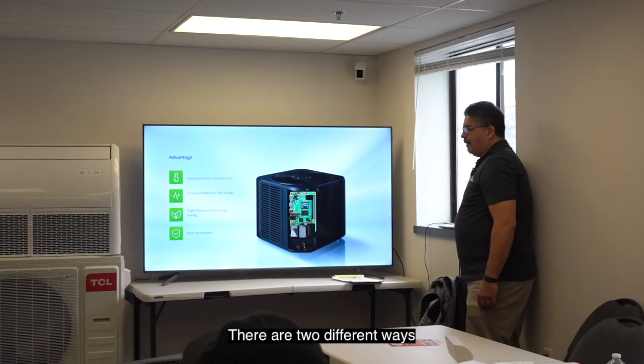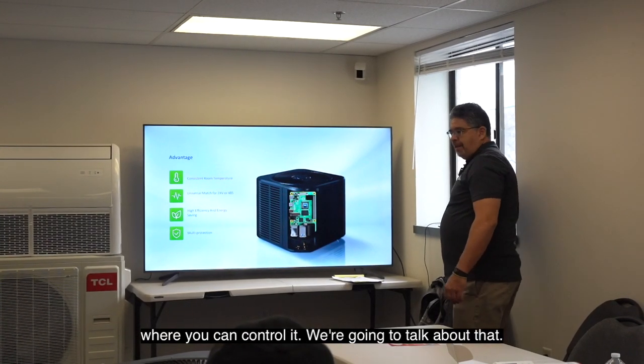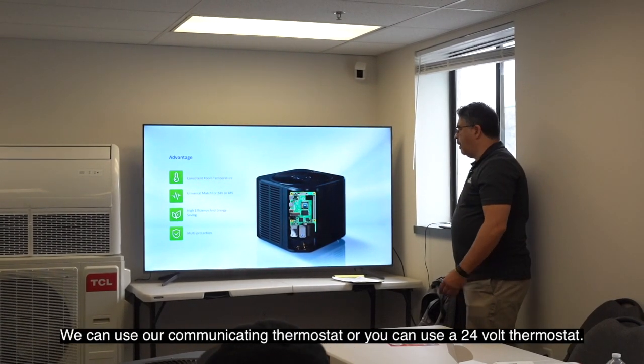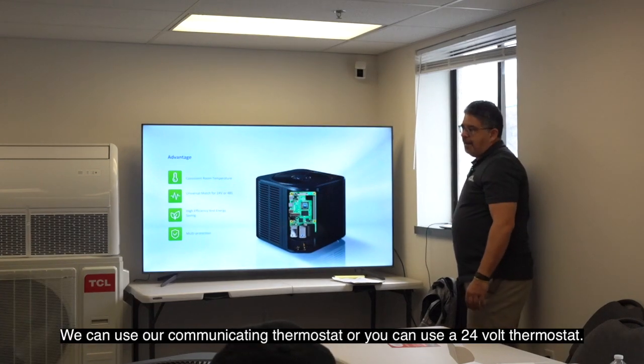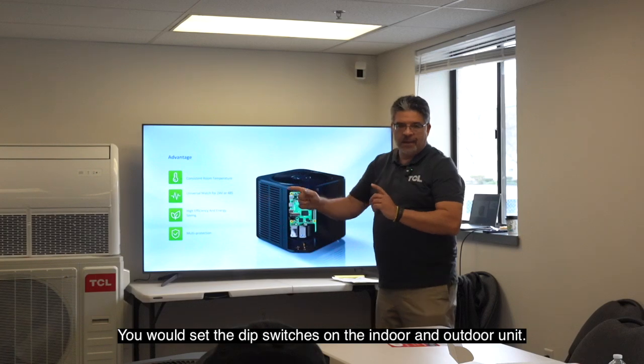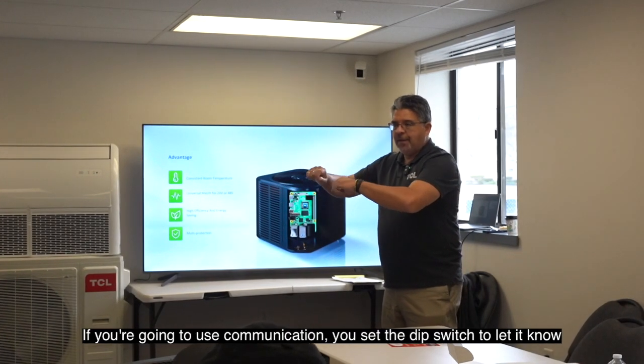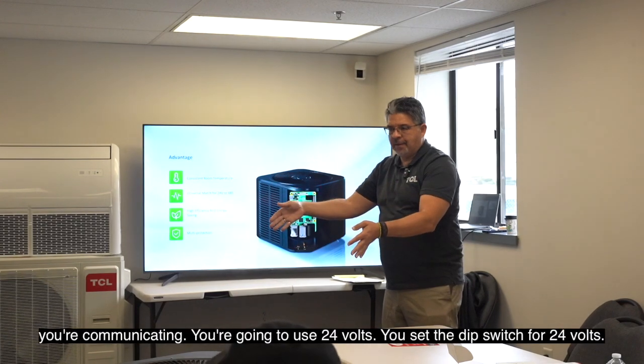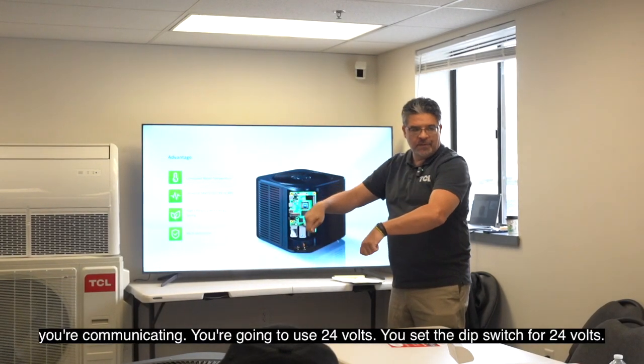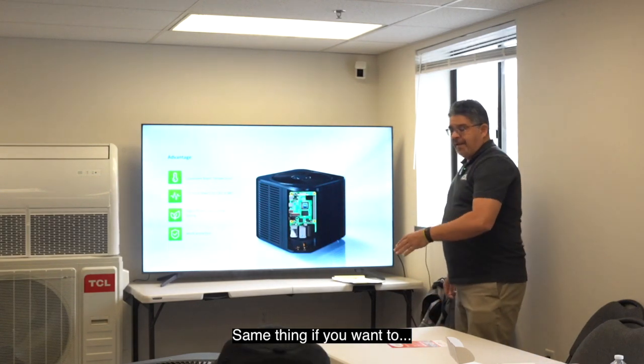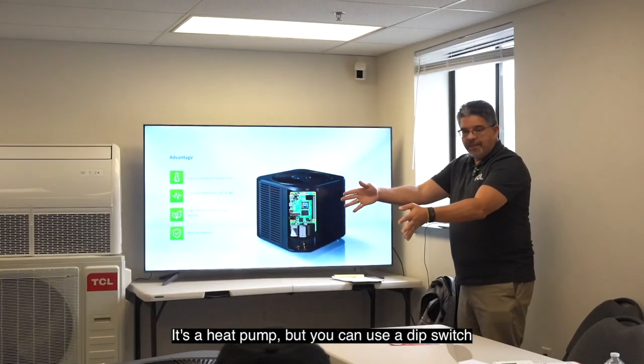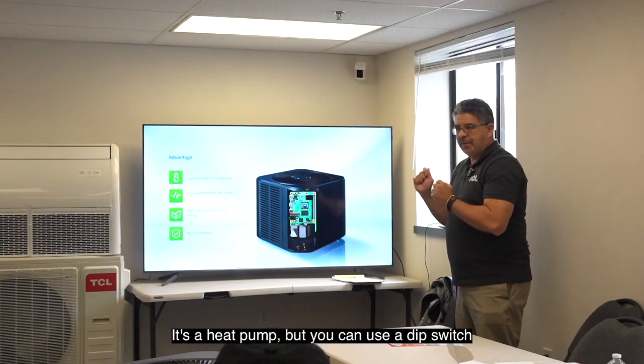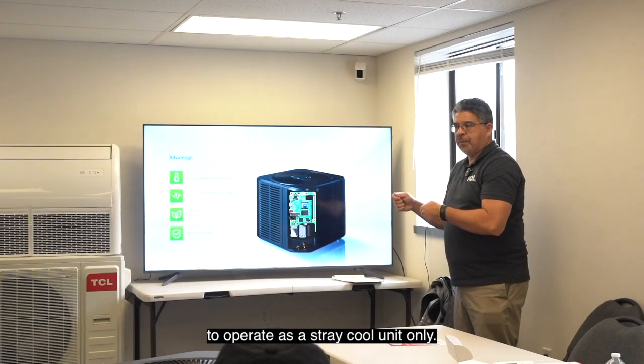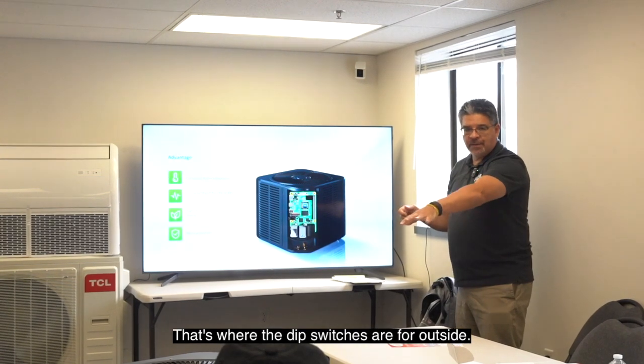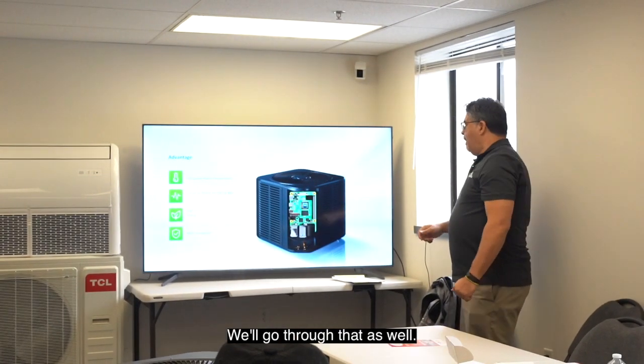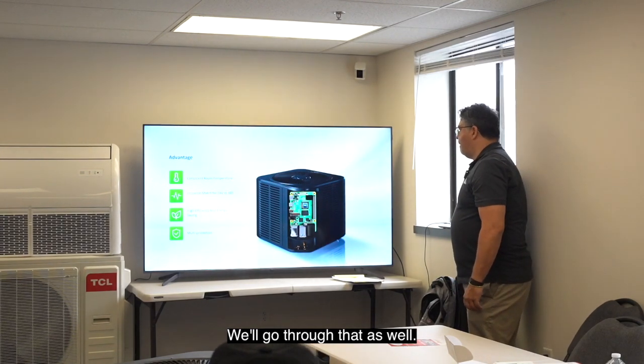All right, there are 2 different ways you can control it. Well, we're going to talk about that. We can use our communicating thermostat, or you can use a 24-volt thermostat. You would set the dip switches on the indoor and outdoor unit. So if you're going to use communication, you set the dip switch to let it know it's going to be communicating. If you're going to use 24 volts, you set the dip switch for 24 volts. Okay? Same thing if you want to, it's a heat pump, but you can use a dip switch to operate as a straight cool unit only. All right? That's where the dip switches are for outside. We'll go through that as well.